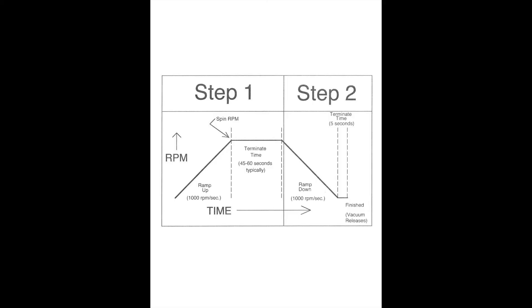Each step has just three things you will be entering: speed, ramp, and terminate time. In a typical two-step recipe, the first step will include the speed which you want to get to, the acceleration rate to get to that speed entered in RPMs per second, and then the length of time that you want it to hold at that speed.